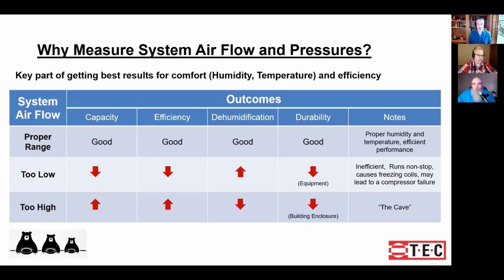expected. Efficiency is better, but dehumidification goes way down. And that, better capacity and better efficiency might sound like good things, but not at the expense of dehumidification. It depends on the climate quite a bit. If you're in a humid climate, you don't want your airflow to be so high that you're not doing any dehumidification, because what's going to happen there is now you're going to have problems with humidity, mold growth, and actually the durability of the building enclosure could be at risk. I think I get it. You're just pulling all this outdoor humid air in and just blowing it past that indoor coil, but too fast. And a lot of humidity just goes out through your ductwork, right? Yep. Yeah, exactly. So you're just not getting the humidity out.